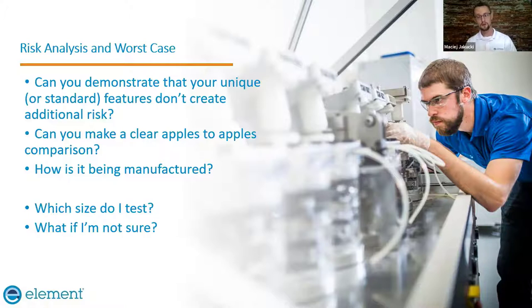I was working with a company with a standard hip stem. They picked their smallest device, ran through some analysis, and made a last second design change close to a high stress region. It was mostly an aesthetic change. They manufactured their devices, did everything right, and expected everything to pass. Then 50,000 cycles into a fatigue test, the stem breaks. There's a bit of a panic, you're trying to figure out what happened. You're running six or twelve of these in parallel depending on what you're doing. The second one breaks at 75,000 cycles, the next one breaks at 80,000 cycles, right through where that aesthetic feature was.